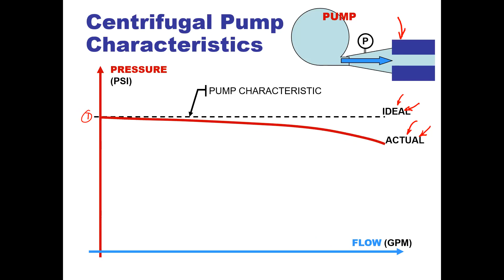But in actuality, we exist down here. This is what we're seeking, this is what our reality is taking us. The red line is our pump characteristic line, it is what we get. With our y-axis of pressure and our x-axis of flow, we are going to be sitting at whatever pressure is here, and as we get more and more flow, our pressure is going to fall off just a little bit. Now we have a system characteristic.